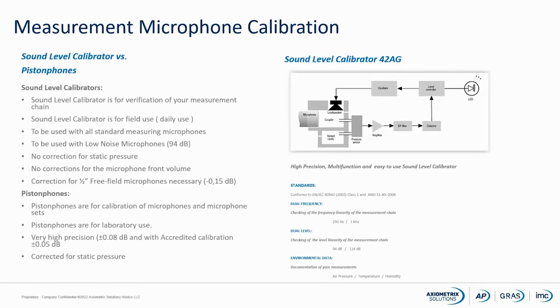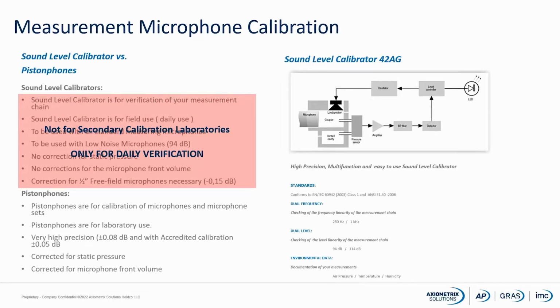You have, of course, with a pistonphone to correct for the static pressure. You also have to correct for the front volume of the microphone. So it is a little bit more difficult to use a pistonphone than to use a sound level calibrator. And it's also the reason why a sound level calibrator is for daily use, and it is for verification to ensure that the whole measurement chain is measuring correctly. So the sound level calibrator is not for secondary calibration laboratories, but only for daily verification, while the pistonphone is a laboratory instrument for secondary calibration laboratories.